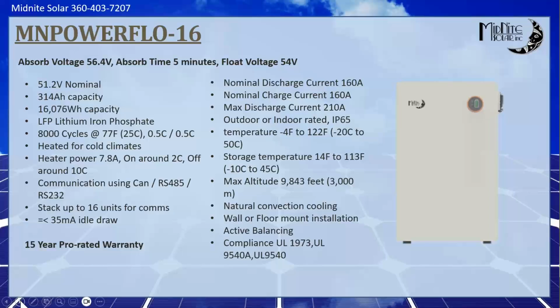Also the same comms. You can stack up to 16 units. These batteries are either wall mount or floor mount instead of rack mount. So you can actually set them on the floor or you can mount them on the wall. There is a spacing requirement. We say 12 inches. Some places will make you go up to 3 feet depending on all the listings. I think some of the California requirements are pushing you out to like 3 feet of spacing. So definitely know your requirements there from the AHJ.